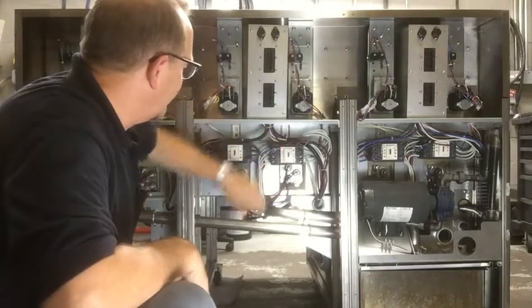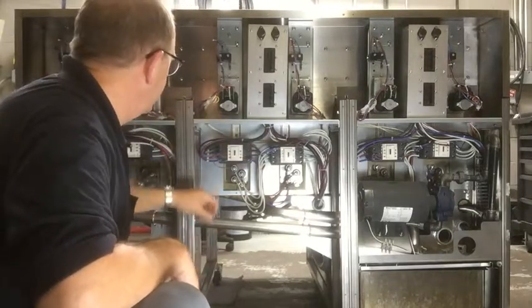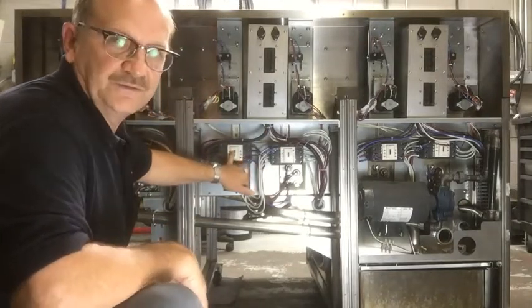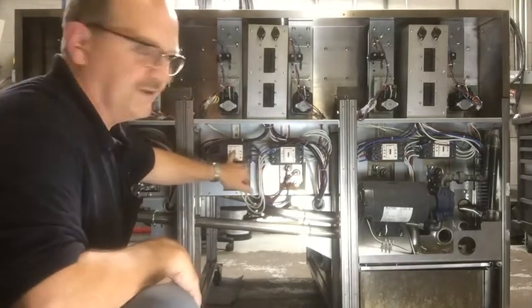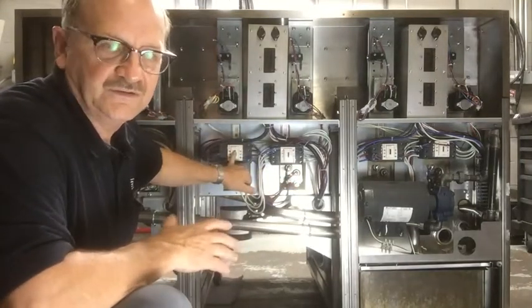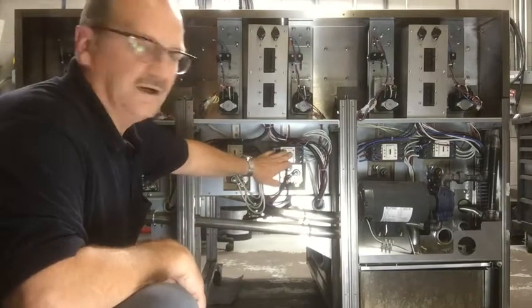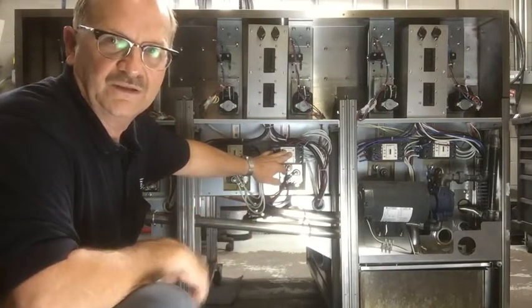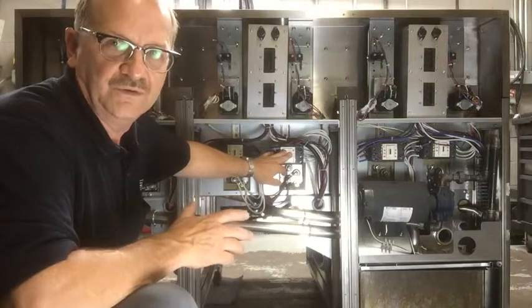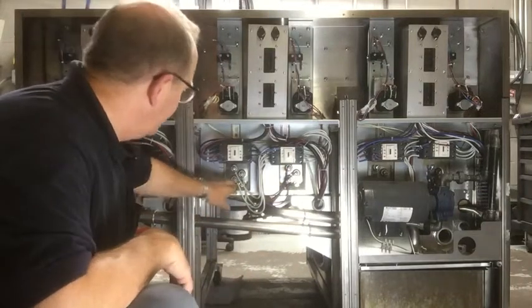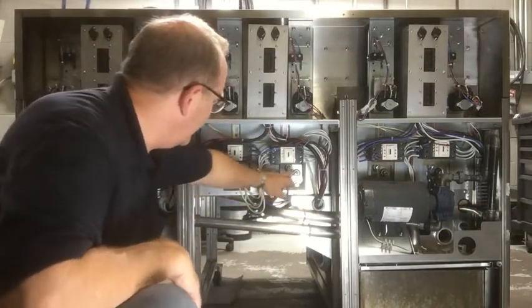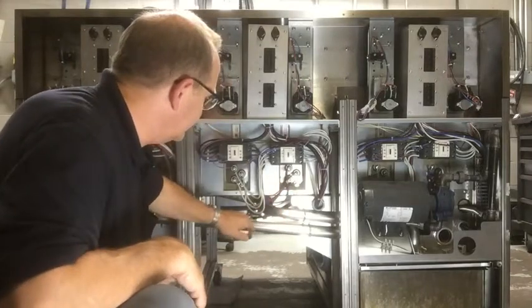We have our two contactors here at the bottom. This is our safety contactor, our heat contactor. The safety contactor will drop out in the case of a high limit. The heat contactor comes on and off to regulate the temperature of the oil as it's required. Heat elements all wired in right here. Notice they're easy to get to.